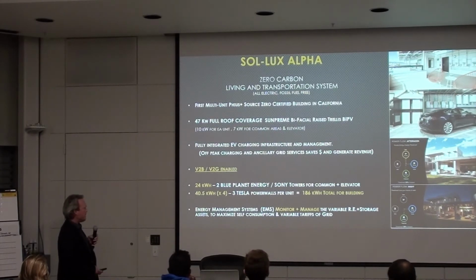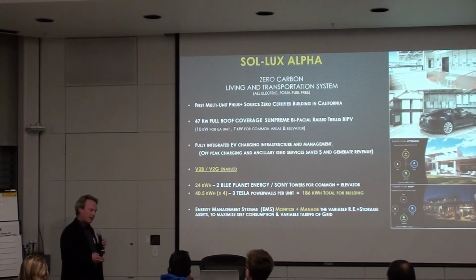The energy management systems are proprietary to each of those systems, and they monitor and manage the variable renewable energy storage assets. We have them set to maximize self-consumption and the variable tariffs, but you can adjust that to customize, and you want to preset your reserve amount. We have these set to 20% reserve all the time, so if the battery drains down and the grid goes out, you still have 20% capacity to get through the night or day cycle.